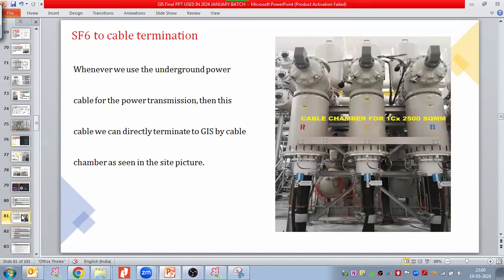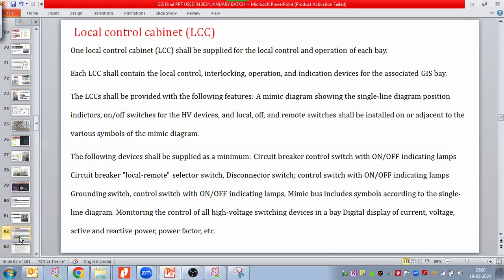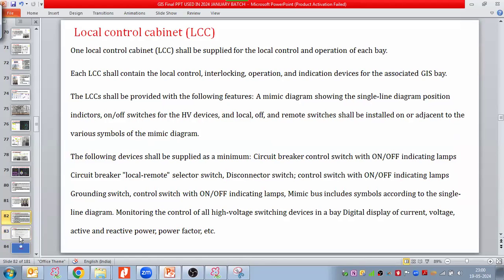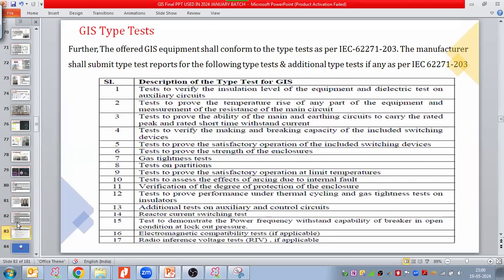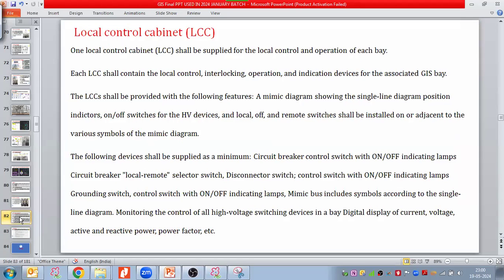If we are taking an underground cable, then we take a cable chamber into the GIS and terminate the cable to the GIS. Right? Then we have the local control cabinet. About the local control cabinets and about the type test, let us discuss this point as well.